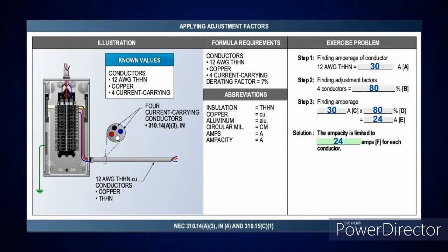So, dude, we had one today, which I think you'll be interested in. Someone said that you size it off the 60 degree insulation rating, like if you're on an NM cable, he said it's 60 degree insulation rating, and I don't think that's correct. No, that's not. What he's talking about is once you do the 90 degree C and you derate off of that, then you're looking to make sure that you have enough amperage to protect that load in the 60 degree C column. And if he didn't explain it that way, that's once again, he doesn't know what he's talking about.